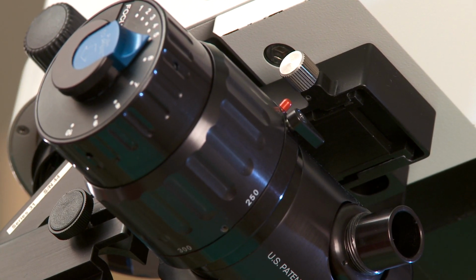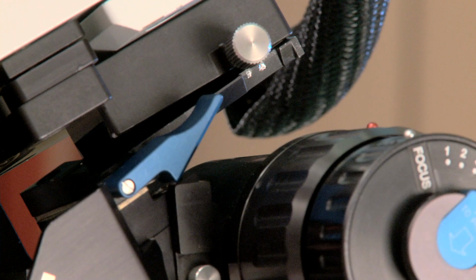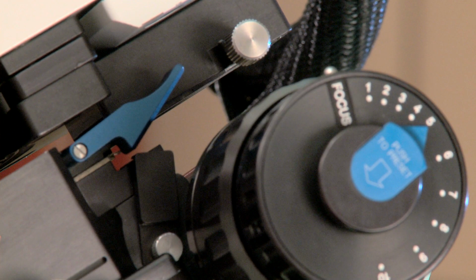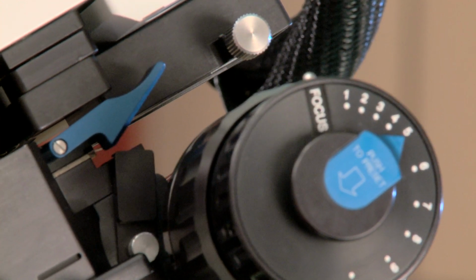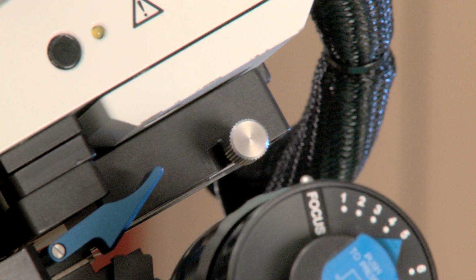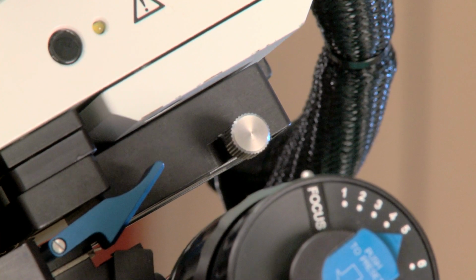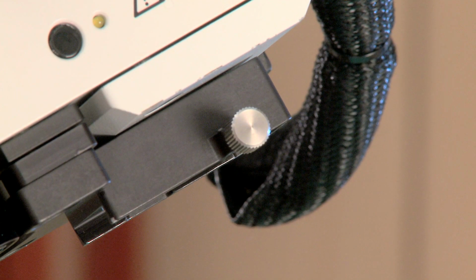The dovetail mount and microscope bracket fit together like a lock and key. To insert the dovetail mount into the microscope bracket, drop one side in first, then push the rest of the dovetail into the bracket, and slide the micromanipulator down until it clicks into place. To release the dovetail from the microscope bracket, unscrew the retaining screw. Lift the blue release lever and reverse the movements.